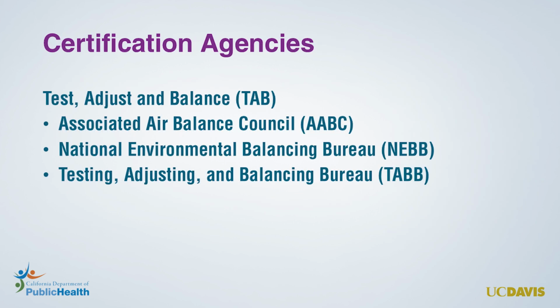When selecting a contractor, we recommend that you require that any test, adjust, and balancing, or TAB, work be completed by a certified technician. There are 3 certification agencies, which are the Associated Air Balance Council, or AABC, the National Environmental Balancing Bureau, or NEBB, and the Testing, Adjusting, and Balancing Bureau, or TABB. Any work completed by the technician should have a complete TAB report and a copy of the technician's certificate.